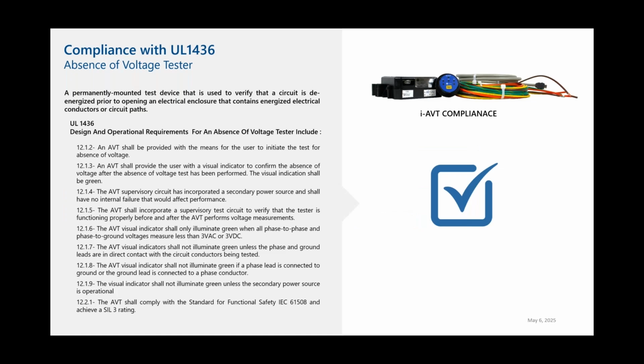So UL 1436 is a standard which dictates the requirements for an absence of voltage tester as well as the design of it. So we'll just go through every step here. An absence of voltage tester shall be provided with the means for the user to initiate the test for absence of voltage. So we accomplish that with the test button. The AVT shall provide users with a visual indicator to confirm absence of voltage, and the visual indication shall be green. So those would be the LEDs on the front of the unit.